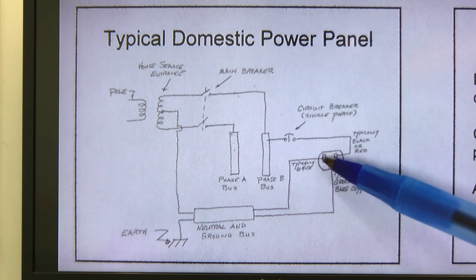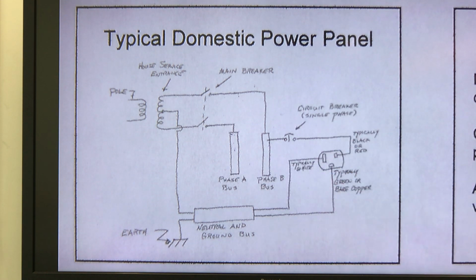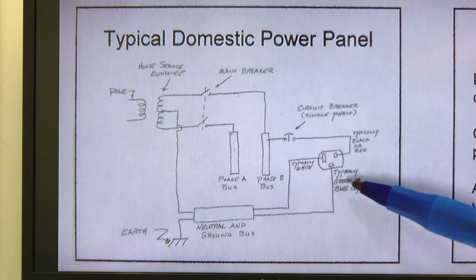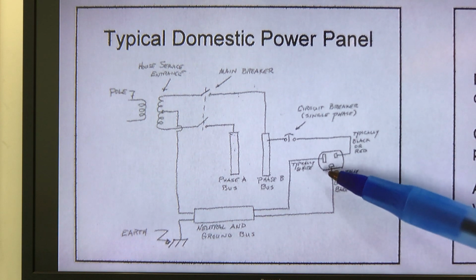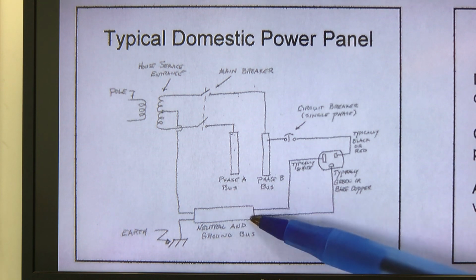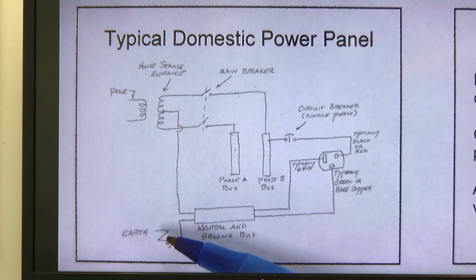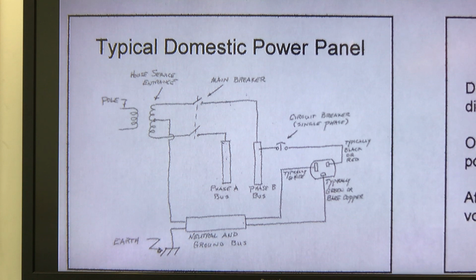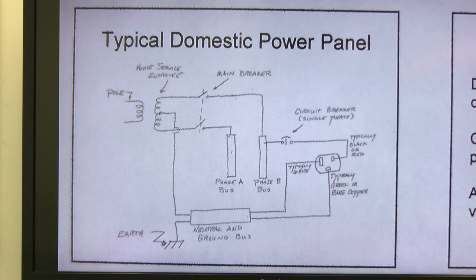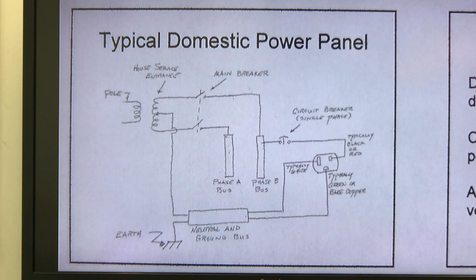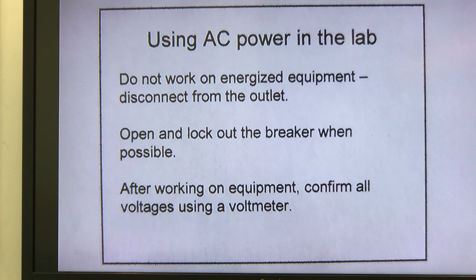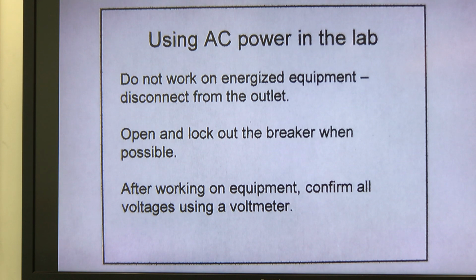Notice too that the neutral goes back to the neutral bus. It is not switched. It should never be switched. It goes back to the neutral bus. And notice also that the ground connection actually returns to the same bus as your neutral. So it's actually a neutral and grounding bus, which ultimately is connected over here to Earth. That's a safety device. It's a safety convention. And when we talk about ground fault circuit interrupters, you'll see why it is the way it is. In terms of the lab, that's pretty much a conventional domestic panel. And as we mentioned in the lab, it's pretty much the same thing.